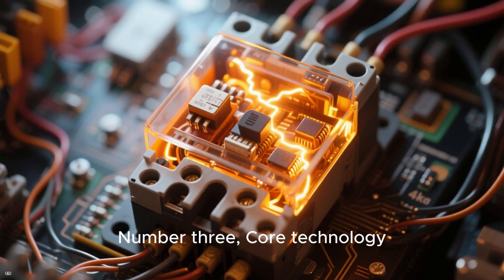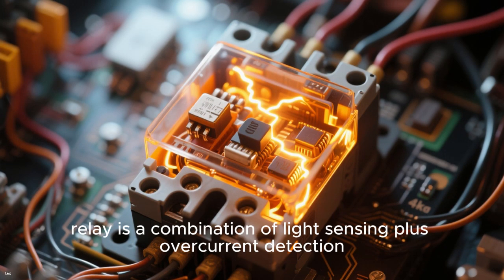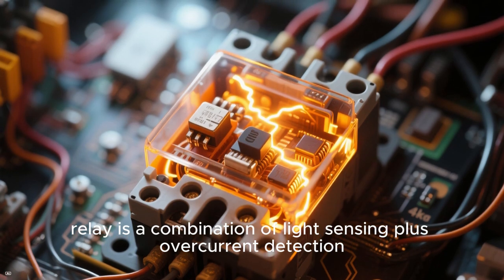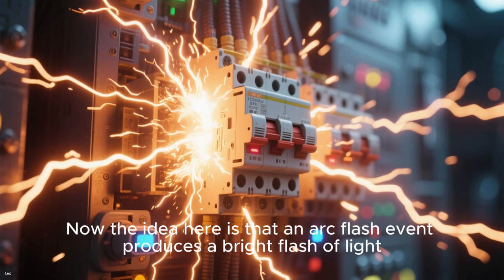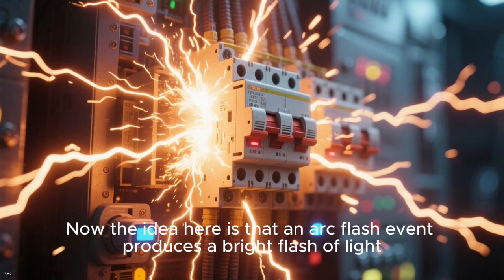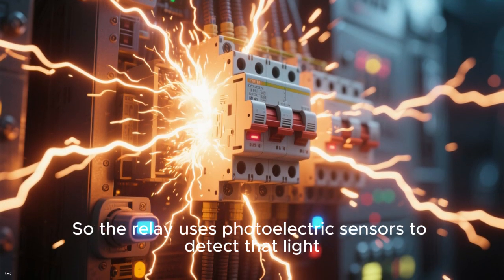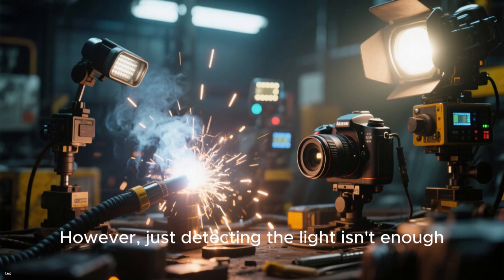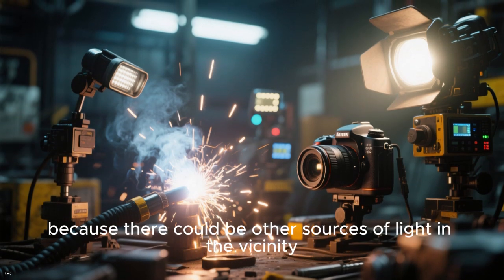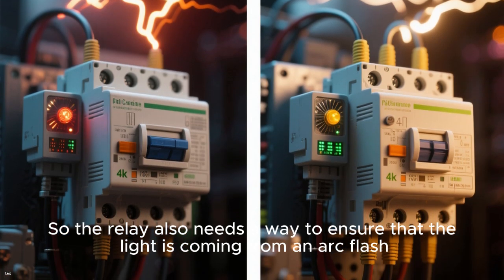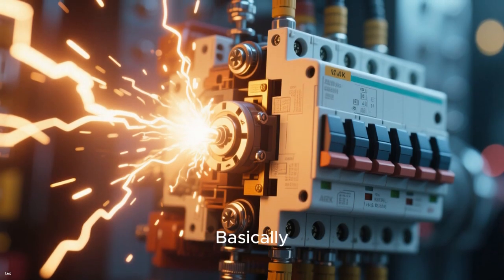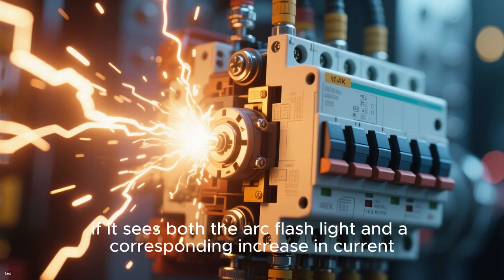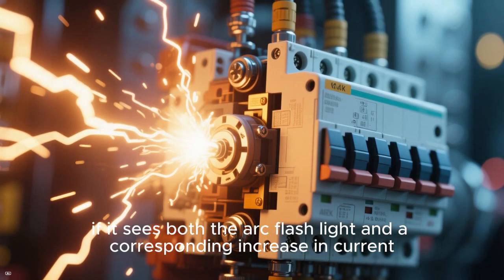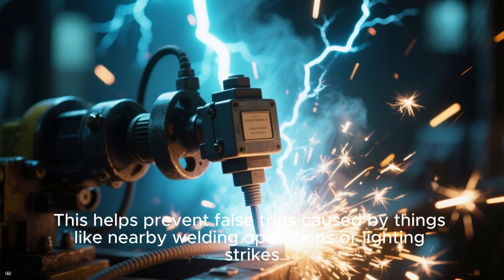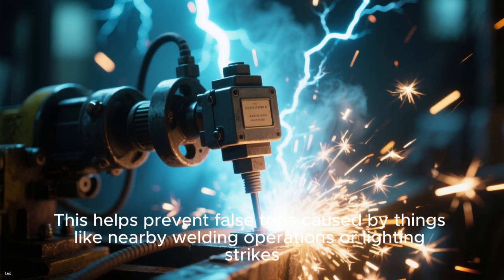Number 3, core technology. At the heart of the arc flash relay is a combination of light sensing plus overcurrent detection. The idea here is that an arc flash event produces a bright flash of light, so the relay uses photoelectric sensors to detect that light. However, just detecting the light isn't enough because there could be other sources of light in the vicinity. So the relay also needs a way to ensure that the light is coming from an arc flash. And that's where the overcurrent detection comes in. Basically, the relay will only trip if it sees both the arc flash light and a corresponding increase in current. This helps prevent false trips caused by things like nearby welding operations or lightning strikes.